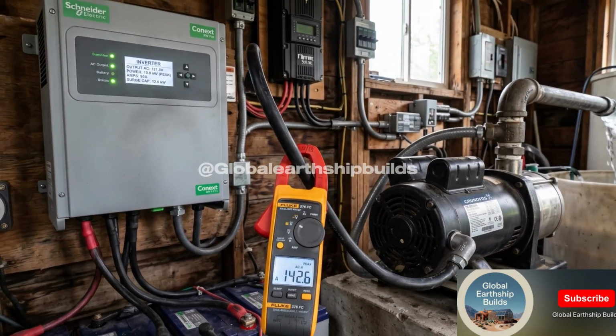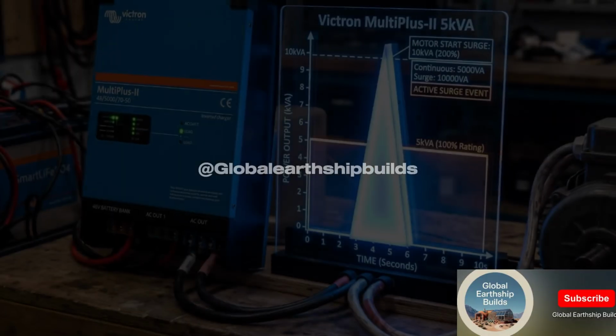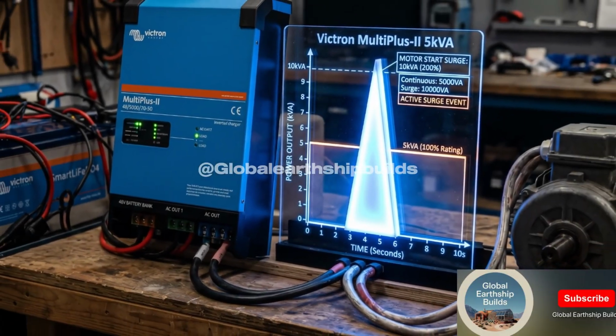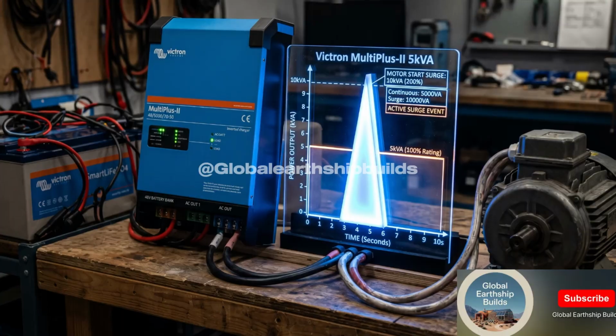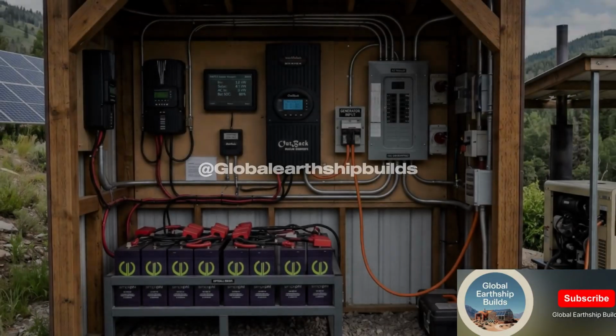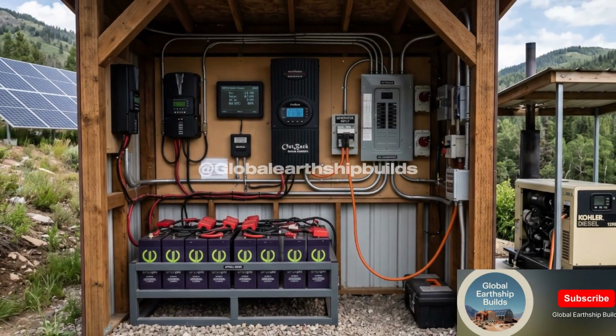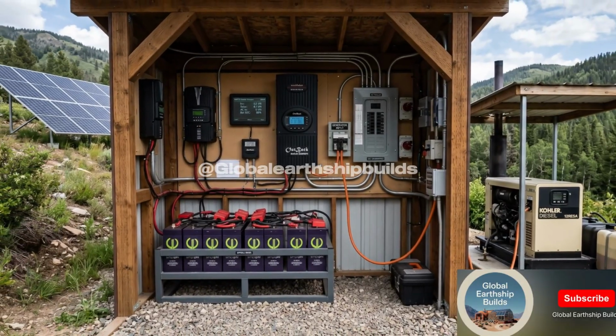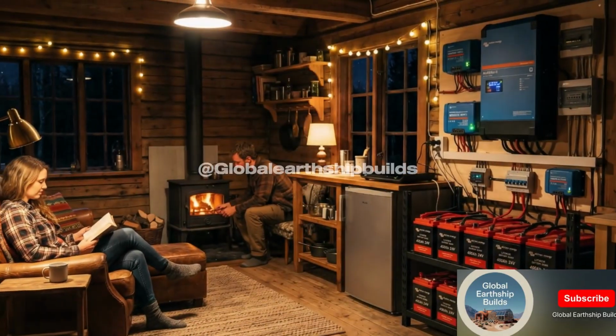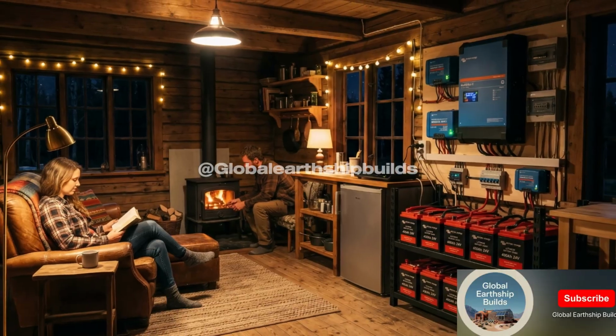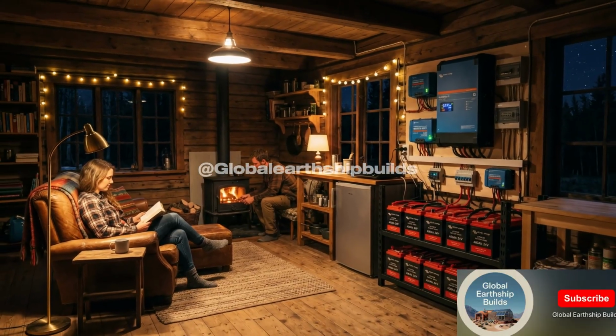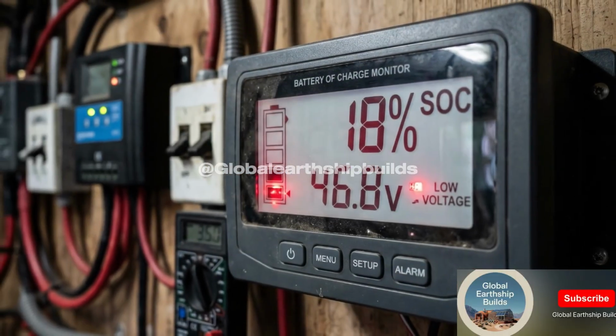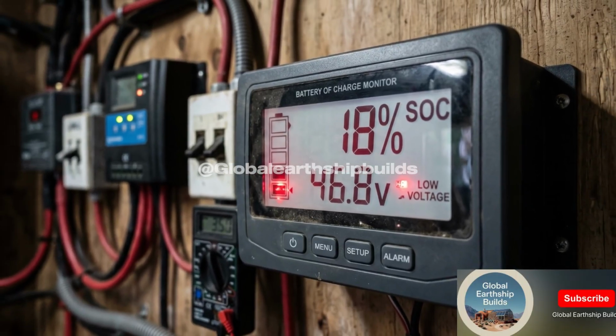The key characteristic of a true off-grid inverter is that it has no grid interaction capability. It does not talk to the grid. It does not export to the grid. It does not pull from the grid during a shortage, when the sun goes down and the batteries drop below your set cutoff. You either have a generator wired in or the lights go out. That is it. The entire energy equation lives inside your own system.